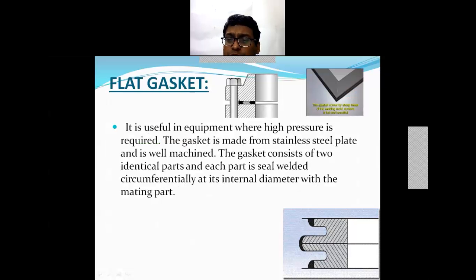Then the flat gasket, you can see this figure. It is useful in the equipments again where high pressure and high temperature requirements are there, because these are all welded gaskets, and generally made of a metal. So as it is welded, it is made from metal. The gasket is made from a stainless steel plate and is well machined. The gasket consists of two identical parts, and each part is seal welded circumferentially at its internal diameter with the mating part.